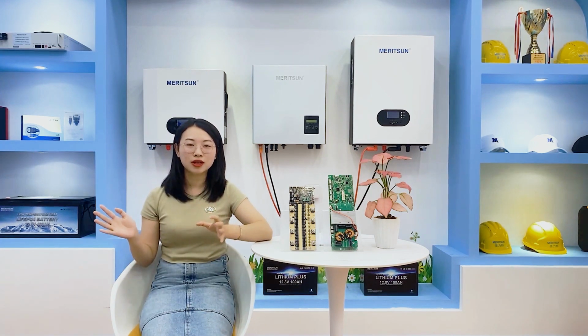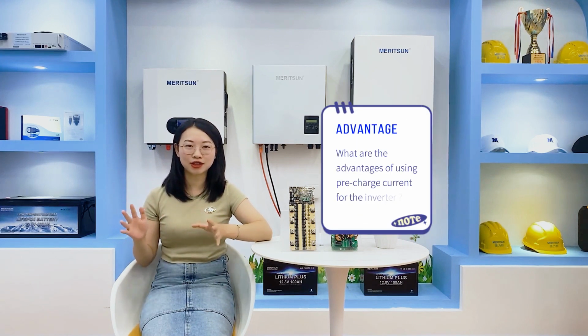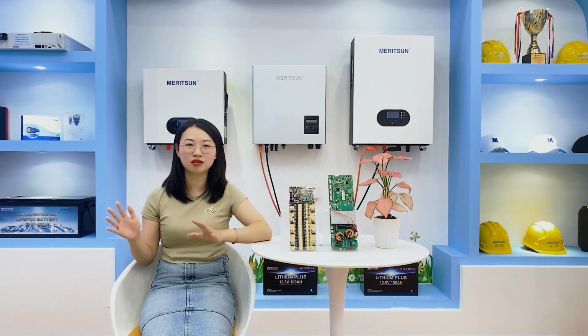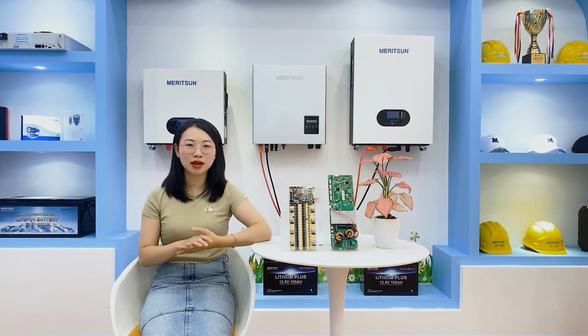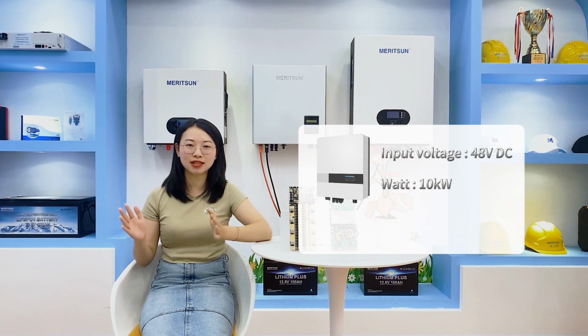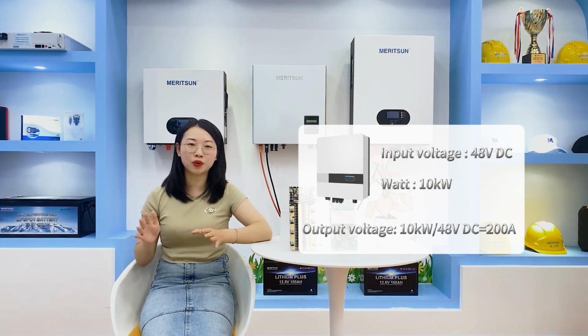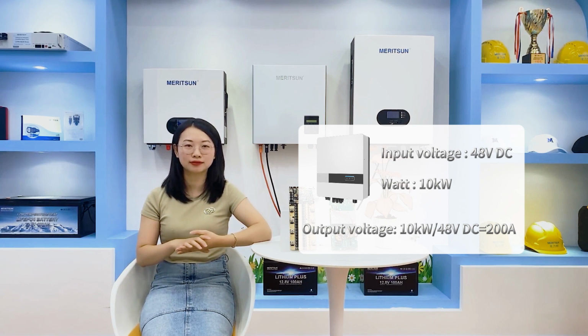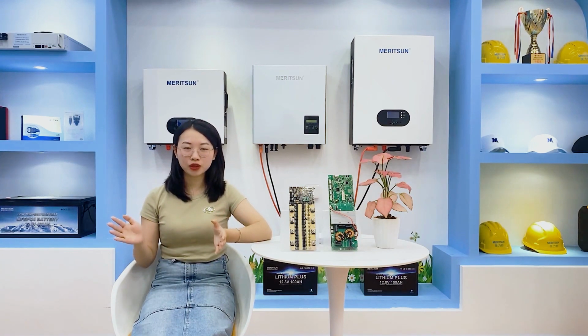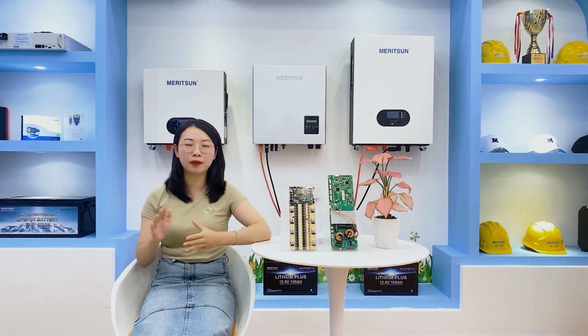So in real life, in a solar system, what are the advantages of using a pre-charge circuit for the inverter? We know that the input current of the inverter is inverter power divided by input voltage. For example, if there is a 48-volt DC 10 kW inverter, then the input current that the inverter can withstand is 10 kW divided by 48-volt DC, equal to about 200 amp. When first connecting a battery to a load with capacitive input, there is an inrush current as the load capacitance is charged up to the battery voltage.